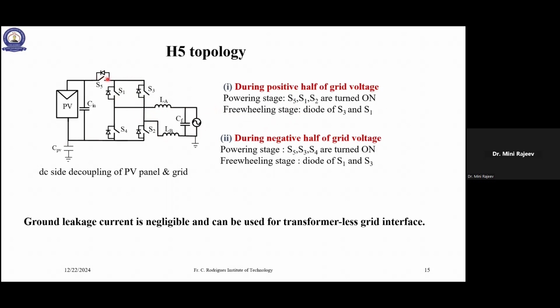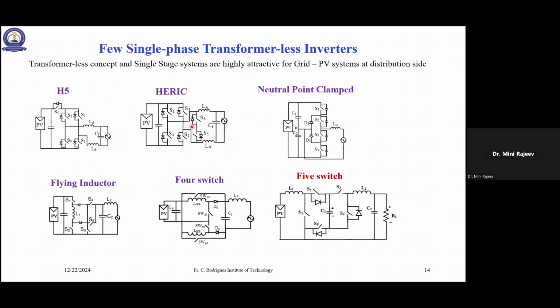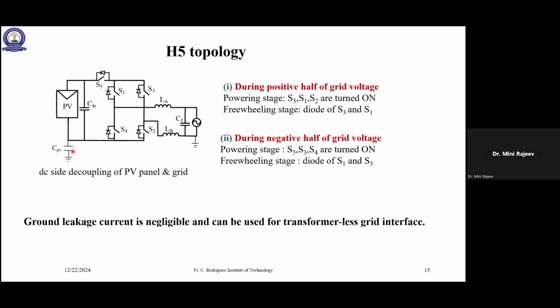So we call it decoupling of the PV panel and the grid. If you keep it open, this will reduce the variation of the common mode voltage, because you are decoupling the AC side and DC side. Similarly during the negative half cycle. This happens in the H5 inverter. Similar thing happens in the HERIC inverter, but on the DC side, it will be decoupled from the DC side during freewheeling operation. So this makes the common mode voltage constant. That is how the capacitor voltage remains constant. Again, C dV by dt: if the rate of change of voltage is zero, the current is 0. That is how they are eliminating the ground leakage current for transformerless grid interface.